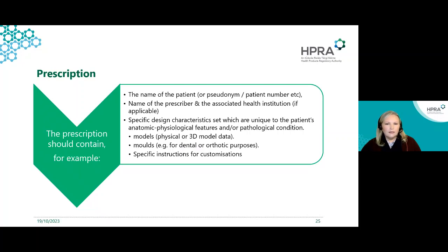But in order to complete the Annex 13 statement, which I'll speak about next, the following minimum elements should be included. The name of the patient or some other means of uniquely identifying the patient. This facilitates the device being provided to the correct person. The name of the prescriber and the associated health institution. This information allows the manufacturer to determine if the prescriber is an authorized person and hence whether they should accept the prescription or not. It also allows for the device to be provided back to the correct clinic or practice for onward provision to the patient or user.